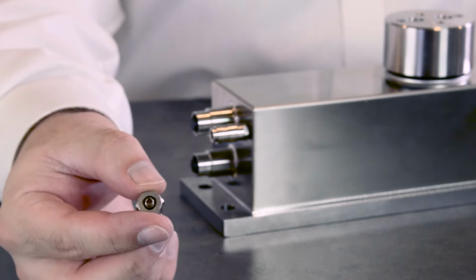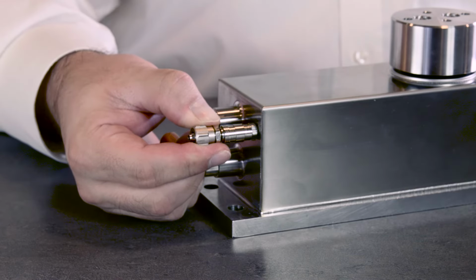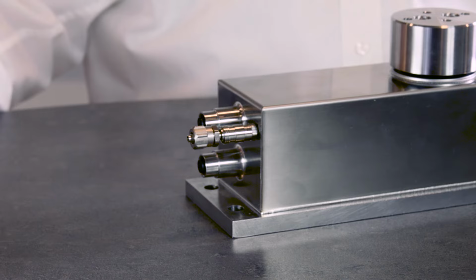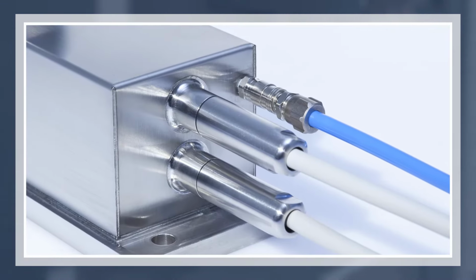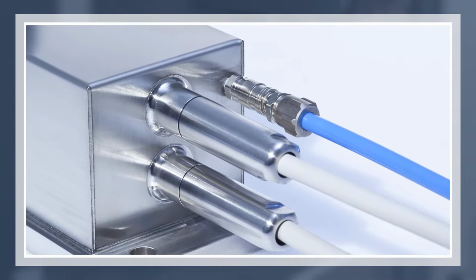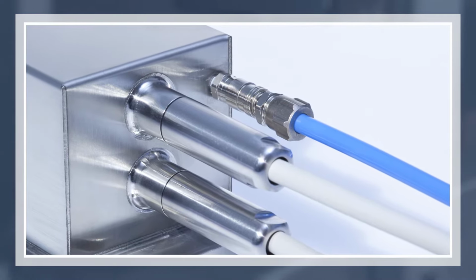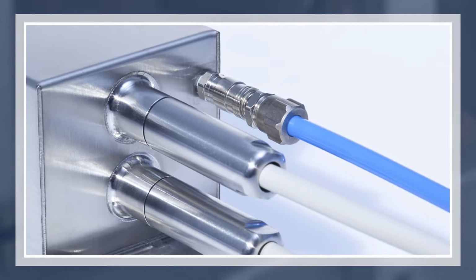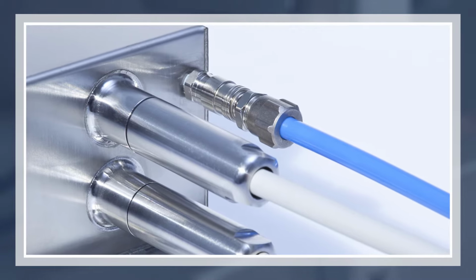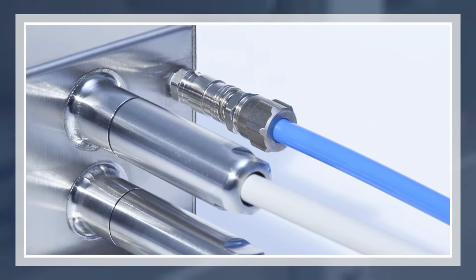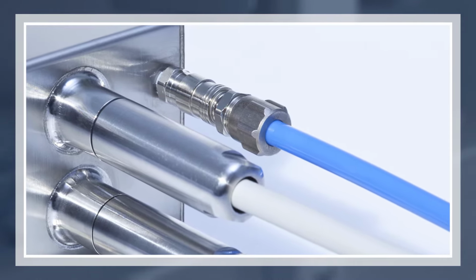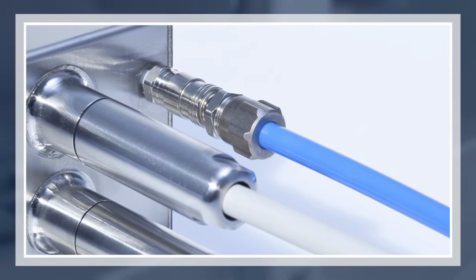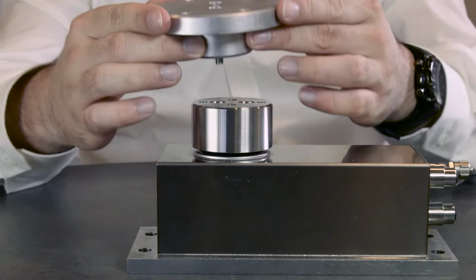It's okay to connect the coupling plug to the compressed air connection if the humidity at the installation location is stable. A standard air hose with a 6 mm outside diameter should be attached at the coupling plug if the humidity at the installation location is subject to fluctuations. The open end of the hose can be routed to an environment with stable humidity, that is, a control cabinet.